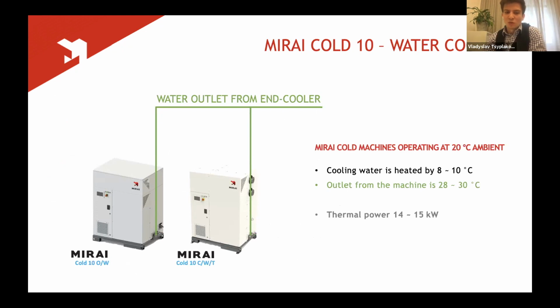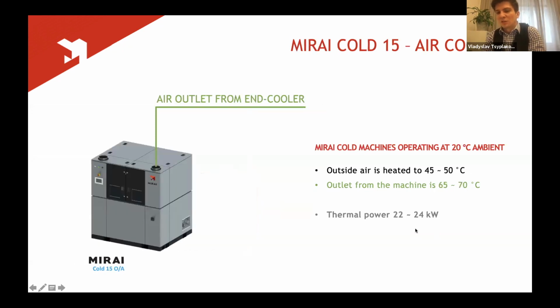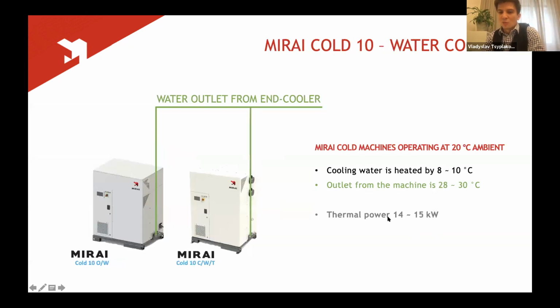But coming down to our products and what type of heating you can get from it, usually from the water-cooled units, you can get the low potential heating. So if, for example, the machines are cooled with the temperature of plus 20 degrees, you can harvest about an additional 8 to 10 degrees of heat. So the outlet temperature would be between 28 and 30 degrees with the thermal power of 14 to 15 kilowatts.